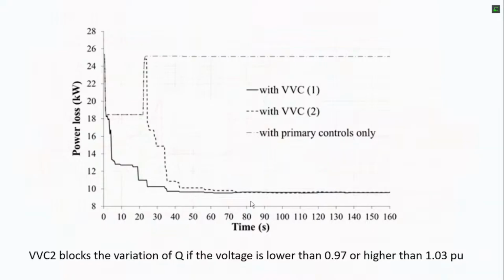You see the decrease of the power loss. During this optimization, the power loss decreases in time. So you see also the times, in several seconds you decrease the losses. This is when VVC1 and VVC2 block the variation of reactive power if the voltage is lower than 0.97 or higher than 1.03, so the V minus and V plus that we considered before.